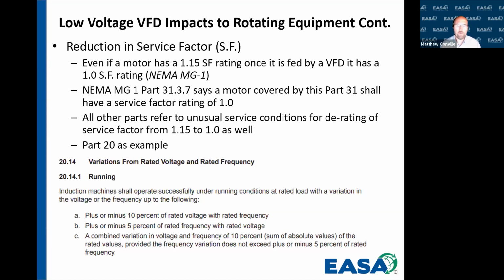So any NEMA motor that's conforming, or any nameplate that conforms with NEMA and it's an inverter rated machine, won't have a service factor. All other parts of NEMA MG1 refer to unusual service conditions that actually take the rating from a 1.15 to a 1 as well. So if we look at Part 20 as an example, it says that induction machines shall operate under normal running conditions at a rated load and a variation in voltage and frequency up to the following. C is where we're worried: a combination in variation in voltage and frequency that is 10%. So if we have a change that's 10%, it's the sum of the absolute values of the change in frequency and the change in voltage, provided the frequency variation does not exceed 5% of the rated frequency.